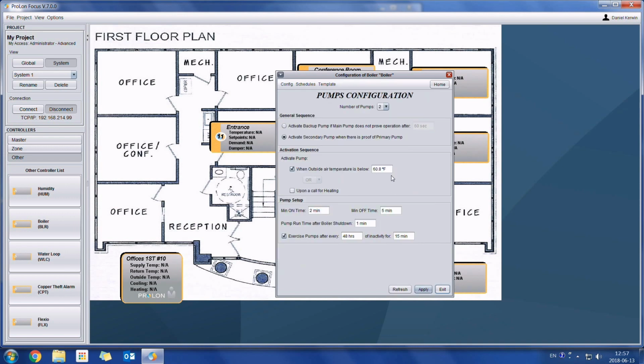We can activate our pumps based on outside air temperature or based on a heating call. When we activate it on outside air temperature, that's basically your freeze protection right there. Or we could turn it on when there is a boiler call.